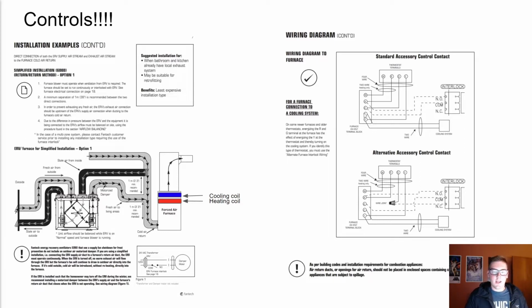And so why I didn't like that is because you can run into 3 operating conditions, 2 of them being bad and only 1 of them being good. If you have this set up such that the ERV turns on the furnace only, that's great when they're both running, but you've got 2 other problems. If the ERV runs without the furnace, and just your furnace fan is circulating that supply air coming from the ERV, you should know that the supply air coming from the ERV is never going to be quite conditioned up to the temperature of the exhaust air because it's not 100% efficient heat transfer. So what that could mean is, let's say in the middle of winter it's 32 Fahrenheit or below out, you've got your 32F air coming in and you've got 70-degree indoor air. That 32-degree air isn't going to be warmed up all the way to 70 degrees.